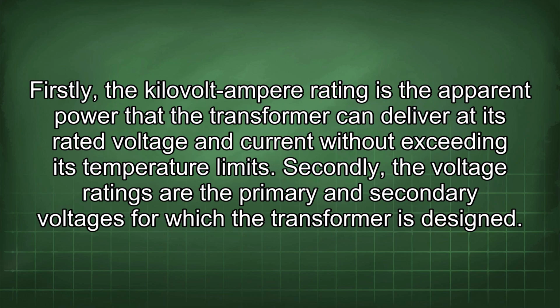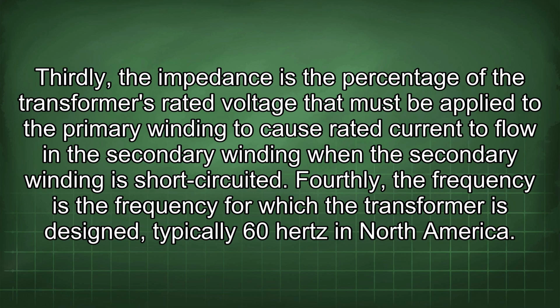Firstly, the kilovolt-ampere rating is the apparent power that the transformer can deliver at its rated voltage and current without exceeding its temperature limits. Secondly, the voltage ratings are the primary and secondary voltages for which the transformer is designed. Thirdly, the impedance is the percentage of the transformer's rated voltage that must be applied to the primary winding to cause rated current to flow in the secondary winding when the secondary winding is short-circuited.